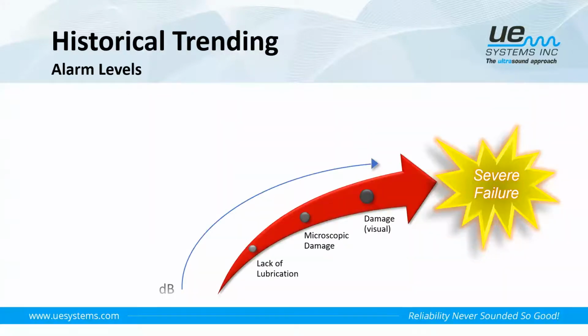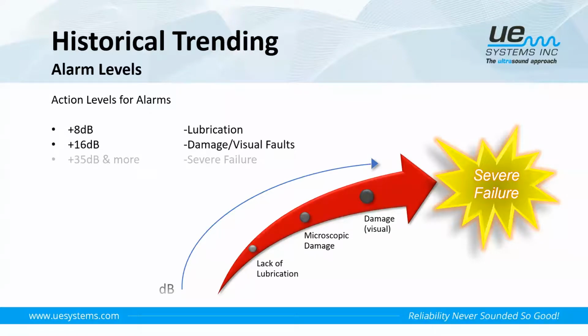So once you've set your baselines, you need to look at setting alarm levels so that you can notify yourself of when certain conditions are met. These action levels for the alarms have been determined over many years of inspections. We've set our baselines, and these next values are numbers above the baseline value. The first alarm level is 8 decibels above the baseline. This could be classed as a low level alarm, and it might be something as simple as requiring lubrication. What we might see here is a smooth, uniform sound that has just increased in level, which highlights to us a lubrication issue.